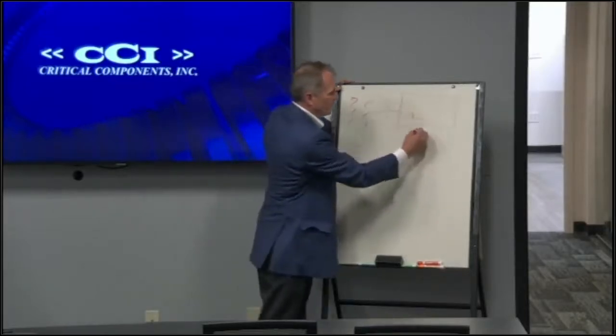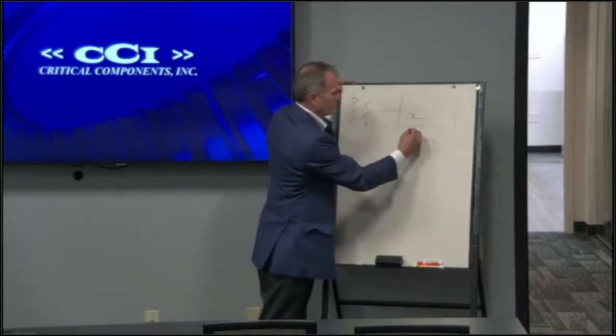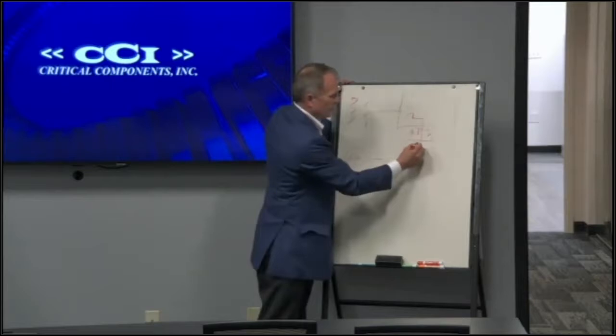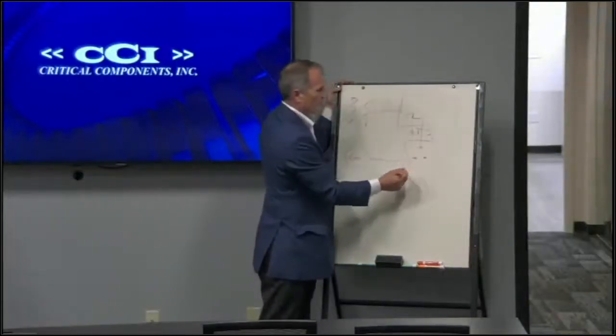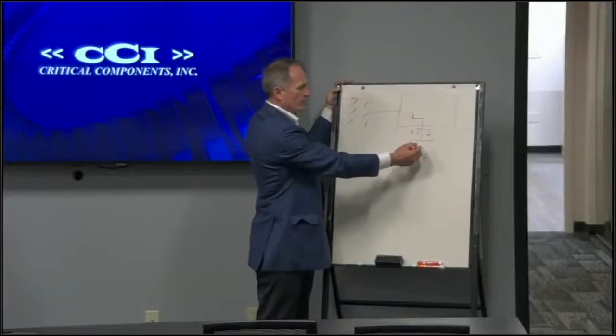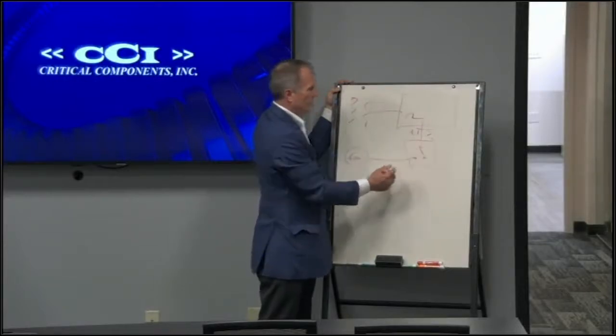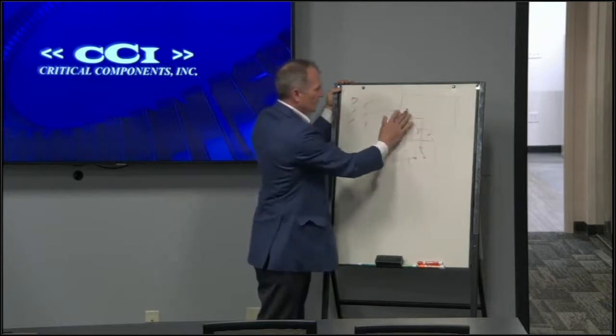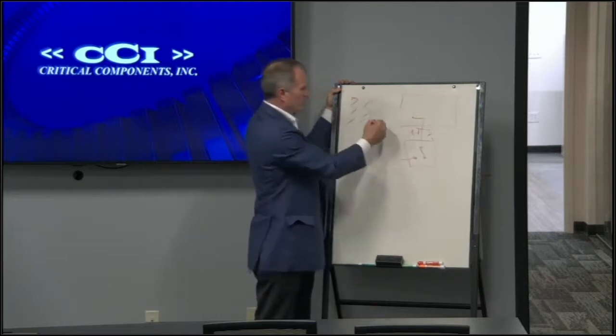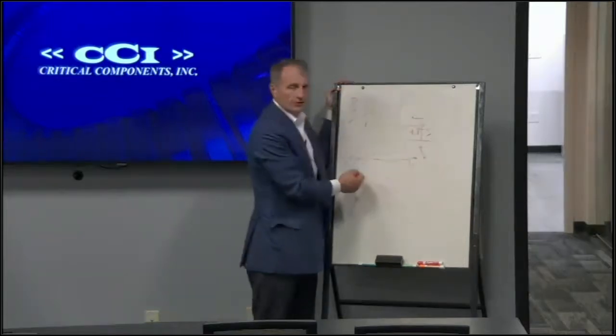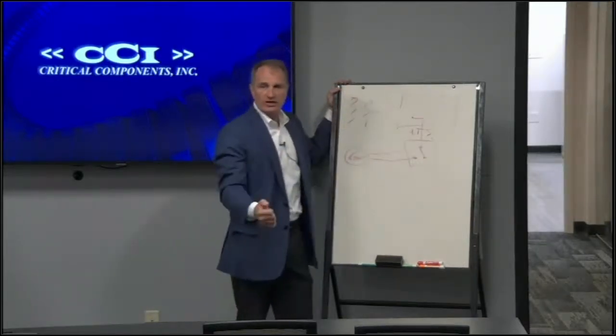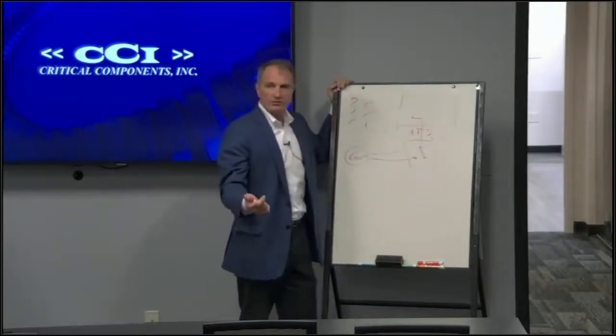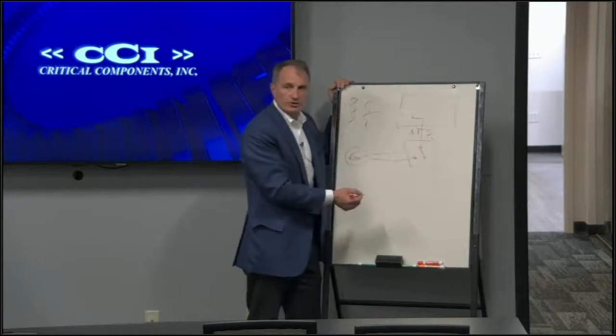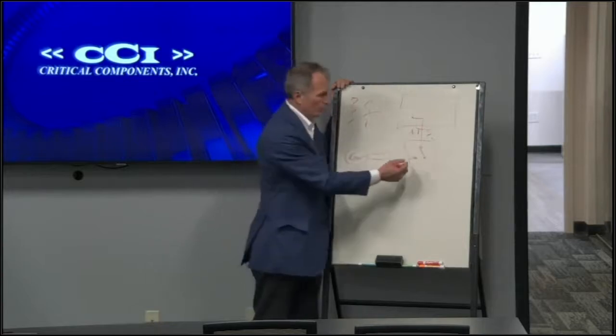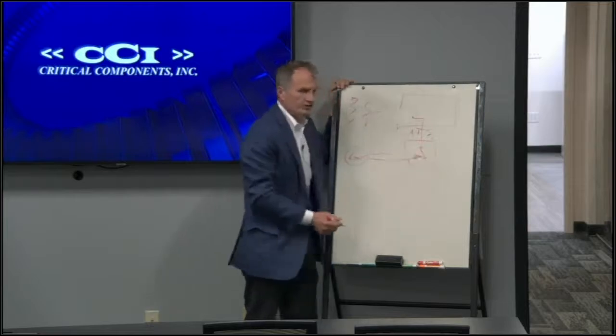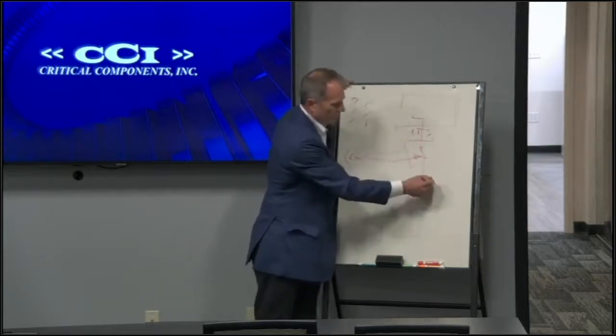So the utility feeds an automatic transfer switch known as an ATS. So this ATS has 2 sources of power to it. Normal power comes from utility through the automatic transfer switch. When utility fails and this power goes away, the generator is sent a signal from the automatic transfer switch. The generator starts up just like turning the key to your automobile. When the generator comes up to voltage and frequency, the automatic transfer switch realizes that it has an alternative source, and the transfer switch will switch to the generator, and this feeds the emergency panel.